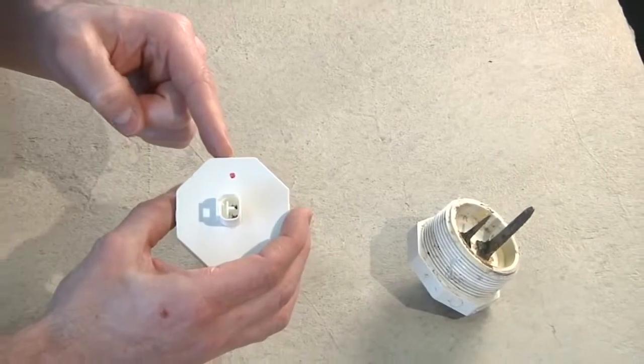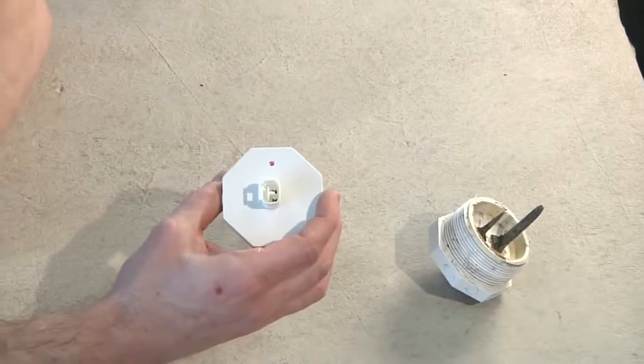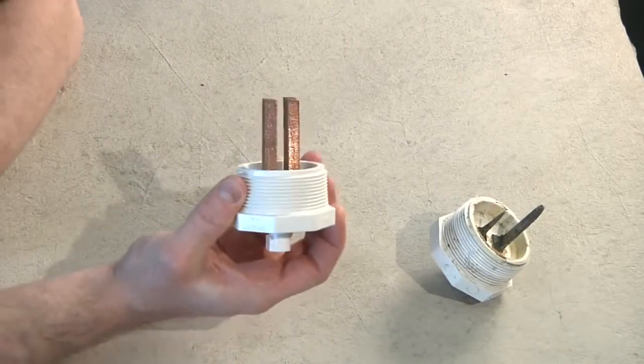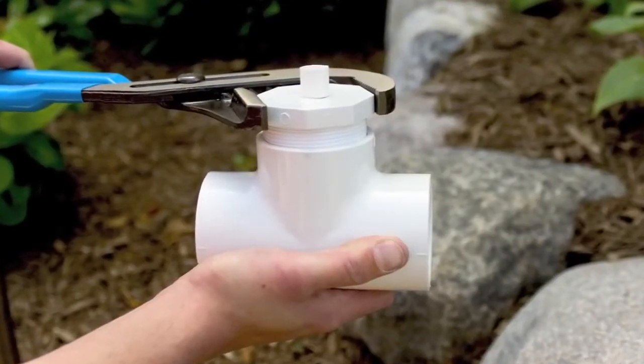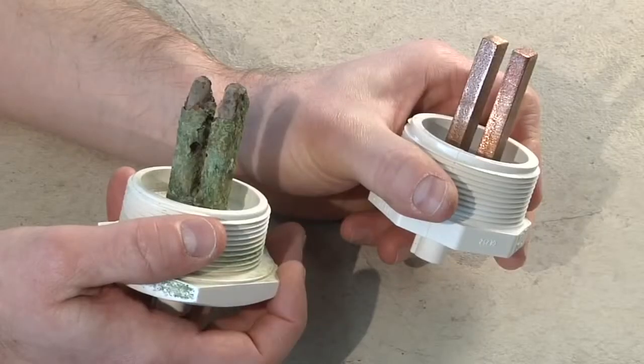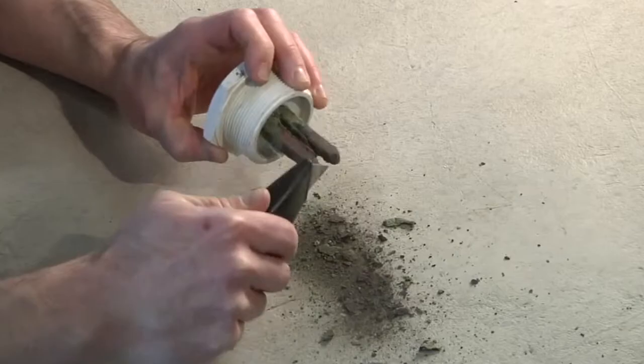There's a small red dot on the top of the probe that indicates the direction of flow. The water should pass between the two bars. Make sure the orientation is in the right direction when reinstalling the probe. If there's still life left in the probe's bars, make sure to remove any scale buildup before reinstalling it.